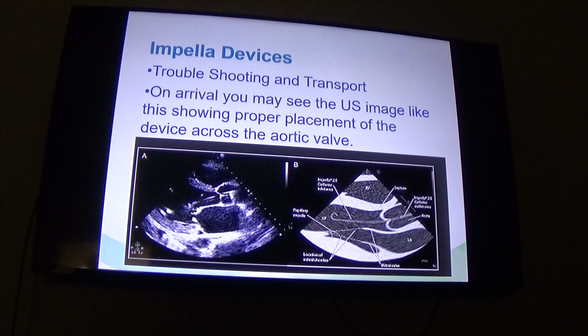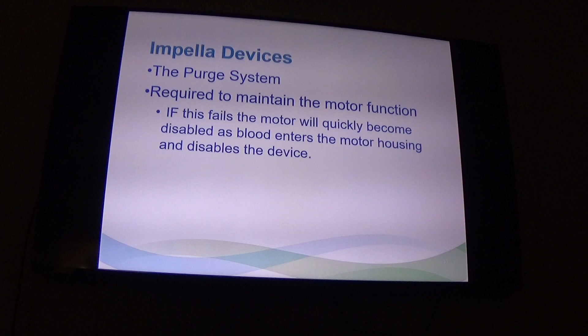The purge solution is required to maintain the motor function. If it fails, the motor will become disabled, the blood will clog up the motor housing and cause it to overheat, and it will stop.